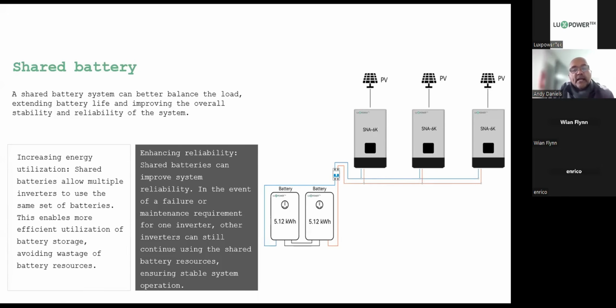So if you connected the batteries in parallel, you created a master and slaves bus bar, and then a master and subordinates on your inverters. It simply means that it will cycle all of the batteries at the same time. You shouldn't end up with unbalanced batteries, unless, of course, you add to a battery bank at a later stage. Okay, so it increases the energy utilization.